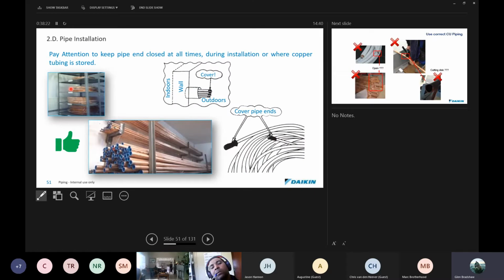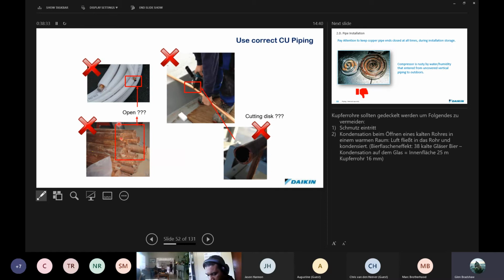Some pointers for pipes. Please make sure that pipe ends are closed at all times, either taped up or crimped and welded. This type of thing is not acceptable. The pipes are open. Here you can see even sand has got onto the pipes. Also, you're not allowed to cut pipes with an angle grinder or cutting disc, as you can throw a lot of debris inside the pipes, both from the copper and from the cutting disc.